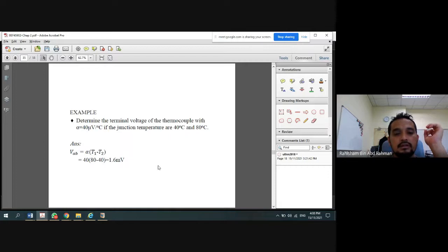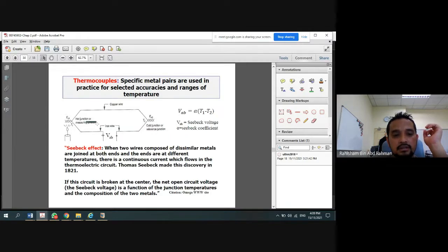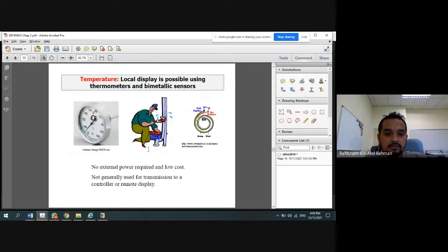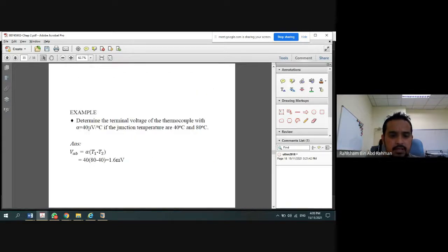This is what it is based on. This is the one that we measured. Okay, if we measure the temperature difference between 40 and 80, we know the voltage will display 1.6 millivolt. If 40 is the reference point, the voltage will give us 1.6 millivolt if the temperature reaches 80 degrees Celsius. Right, so please have a look at this one.